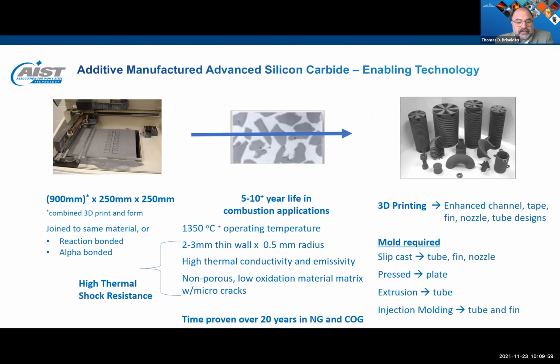So let's dive in. The enabling material platform that pretty much makes everything possible is the ability to additively manufacture advanced silicon carbide. This includes both traditional 3D printing of complex shapes and the use of unique powder extrusions to make large format designs for industrial applications. In some cases, this material will be joined to more traditional materials such as reaction bonded silicon carbide and alpha bonded silicon carbide. In order to achieve energy, carbon, and NOx reduction goals, the material plays a critical role in allowing these designs to operate effectively in extreme environments, namely high temperature to meet all applications, thin walls, high thermal conductivity, and emissivity for excellent heat transfer. A non-porous, low oxidation material matrix is required. These elements combine to help reduce thermal shock, resulting in a perfect material for long-term life in a combustion environment, both in natural gas and coke oven gas applications.